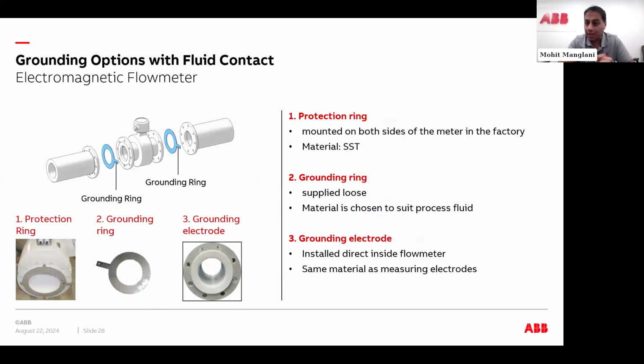So what does good ground look like? What does good cross bonding look like? So in ABB's world, there's 3 ways. You have protection rings, you have grounding rings, and you have grounding electrodes. Number 1, we love protection rings. Protection rings are a way that you can actually mount the ring directly onto the flange of the meter.